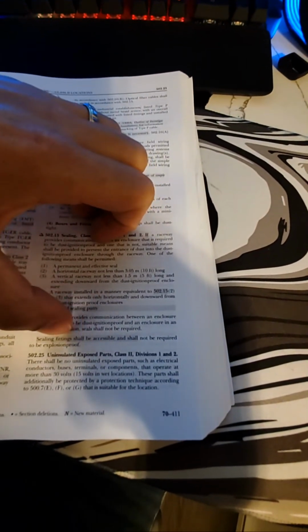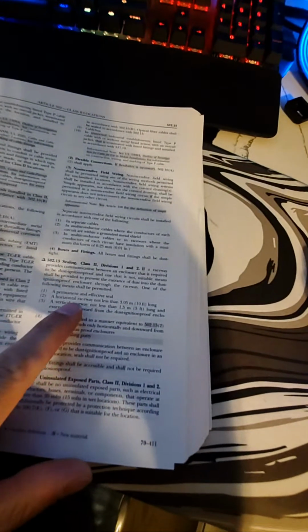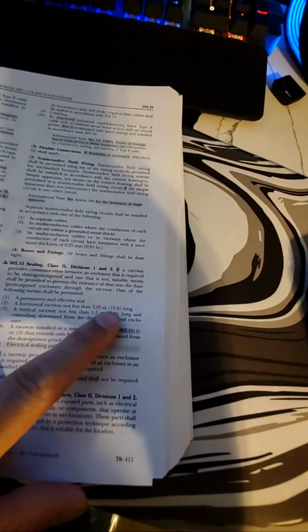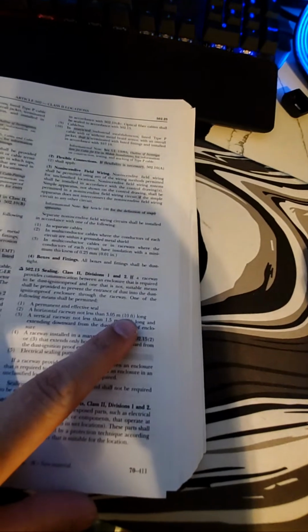The raceway prevents communication between conductors. Sealing fitting shall be accessible. It's 15 feet. Maybe 15 feet is far enough for dust. I feel like it probably needs one. What do you guys think? One or none? It says here, a horizontal raceway not less than 10 feet. So we are more than 10 feet. We're 15 feet.